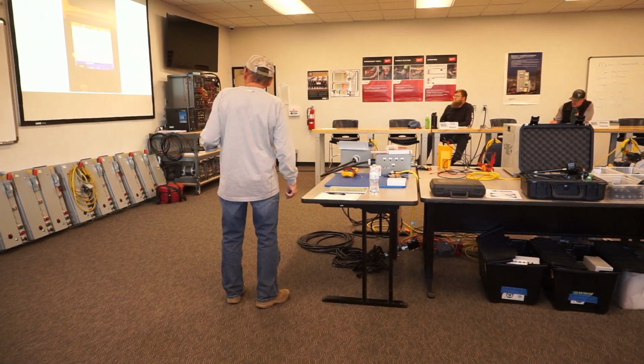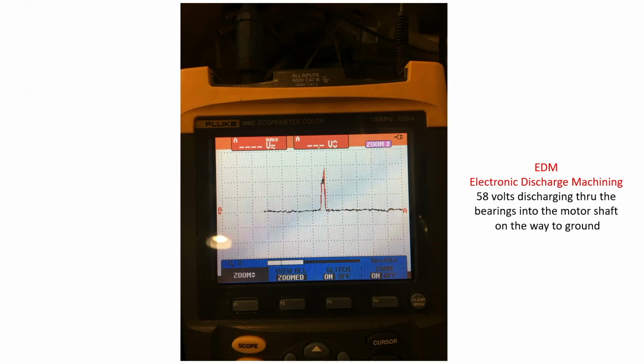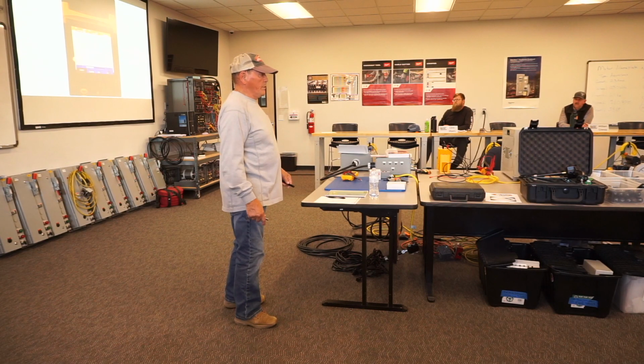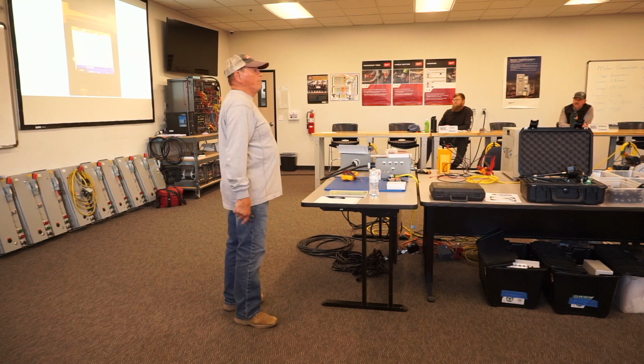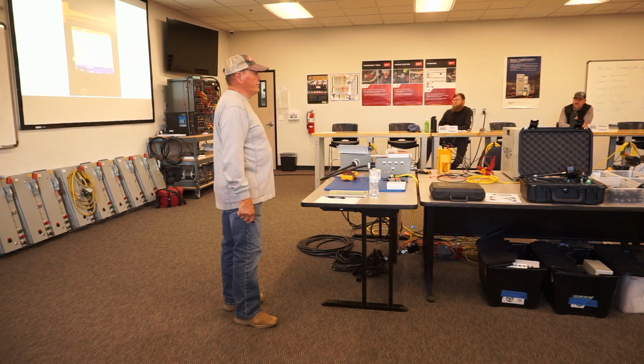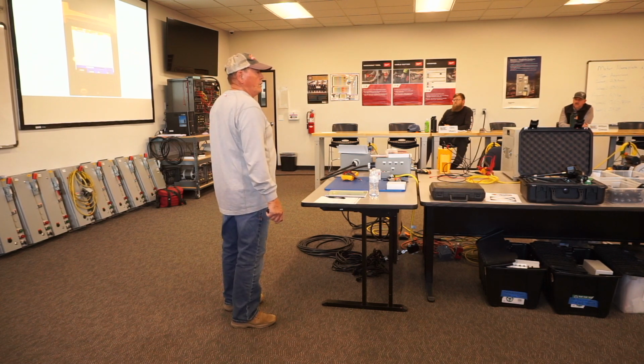58 volts discharging off that motor, through the bearings, onto the shaft of that motor, trying to get back to its source. They were gonna change the bearings on that motor. I already saw a bearing sitting there. Oh, we're getting ready to change the bearings. When I walked in the mechanic room, oh my gosh, it was screaming so loud, it was hurting my ears. He said, oh, no, we're gonna change those bearings. I says, don't bother changing the bearings, because they're gonna go out in another 6 months.